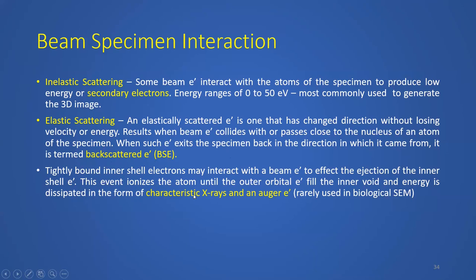And the third kind is when, as a result of the interaction with the electron beam, the inner orbital electrons are ejected and the outer orbital electrons fill the inner void, and some energy is released. So that is the X-rays. For this you need an X-ray spectrometer. This is used for elemental analysis, but rarely used in biological SEM.